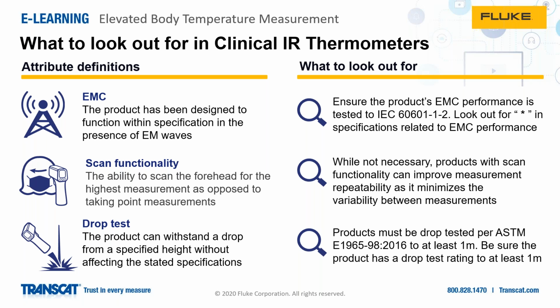While not entirely necessary, you might want to look out for products that have some sort of scan functionality, as this helps improve the measurement repeatability when compared to a spot measurement. So instead of measuring one spot and measuring another, you can hold down the trigger, scan across the entire head, and identify the hottest temperature. Then every time you do a new scan, ideally your repeatability is improved as opposed to just picking different points on the forehead in consecutive measurements. And then finally, you want to look for some sort of drop test rating to ensure that if you drop the product, it's still going to perform within its stated specifications. Under that ASTM standard, the drop test rating requirement is 1 meter. And so you want to make sure you're looking out for products that are drop tested to at least 1 meter.